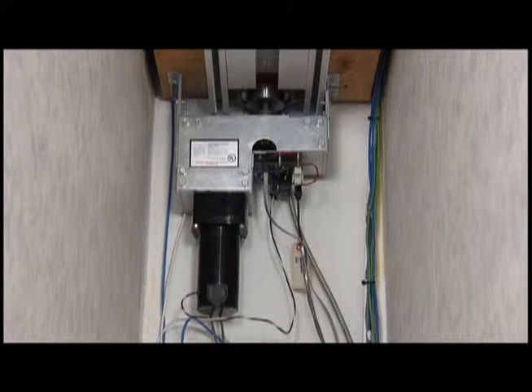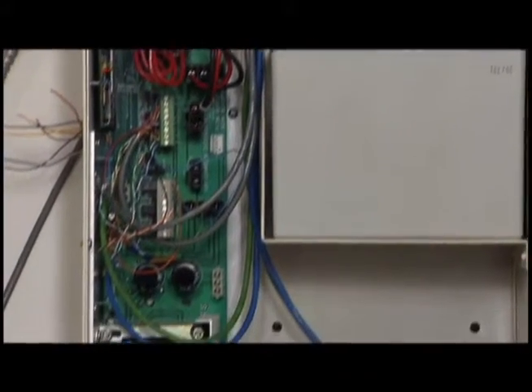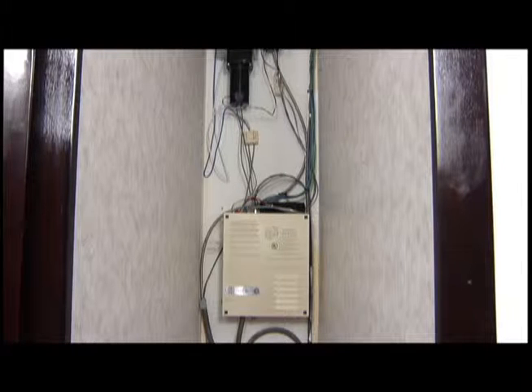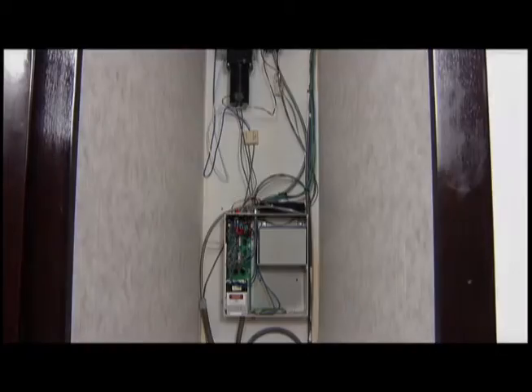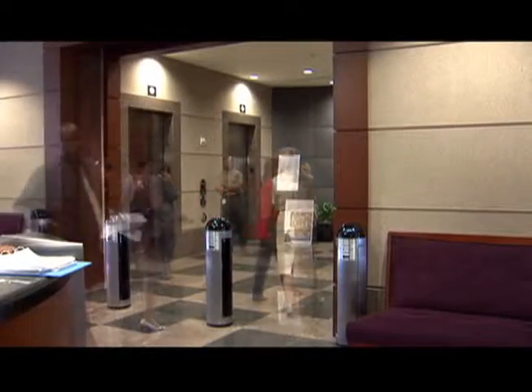The automatic closing system consists of a DC motor, battery, a transformer, and a microprocessor and logic board. This system is protected within a fire-rated enclosure and is typically located at the back of the door storage pocket. The in-house electrical system provides power to continuously charge the battery and allow the system to be completely electronically supervised. With the advent of microprocessor technology and electronic supervision, the Won-Door FireGuard door can offer a unique feature, ensuring its constant state of readiness to respond in a fire emergency.